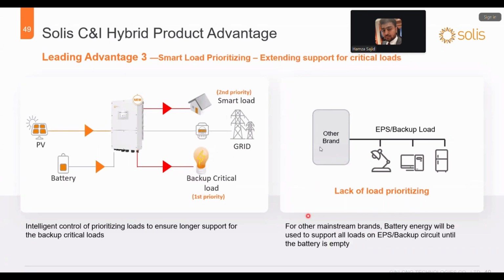And we have the smart port load feature available in this inverter. If you have a second priority load, you can attach it to the Gen port. Other brands don't have this option, so if a grid outage happens, all the battery is drained because they cannot turn off the unnecessary load.